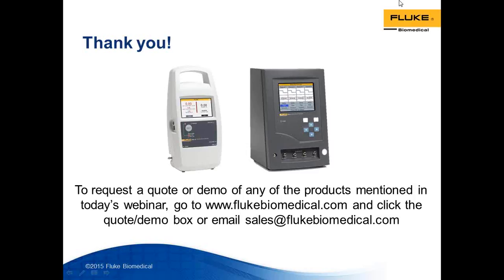Okay, next one. What is the advantage that the IDA5 has over the IDA4 Plus? So we went over some of those advantages a little bit earlier, but I'm just quickly going to go through them again. As compared to the IDA4 Plus, the IDA5 has an expanded range for flow measurement. The IDA4 was up to 1,000 ml. This is up to 1,500, and 2,600 is what it would measure, and you can, but we are only specifying the product to 1,500 milliliters. So don't be surprised if you're testing 2,000 and you see that the product is working great with good accuracy.